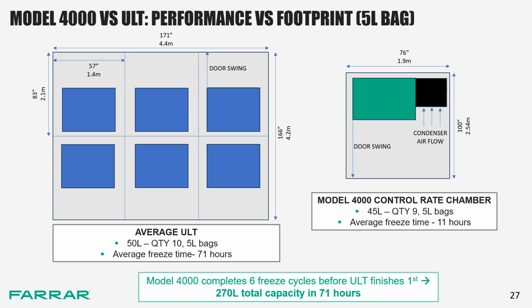In this slide, we're looking at 5-liter bags filled and placed in three different ULT freezer brands, plus the FARRAR control rate Model 4000. The ULTs each could hold about 50 liters or 10 bags, and the Model 4000 holds 9 bags or 45 liters. The average freeze time for the bags in the ULTs was 71 hours, almost 3 days, versus 11 hours in the Model 4000.